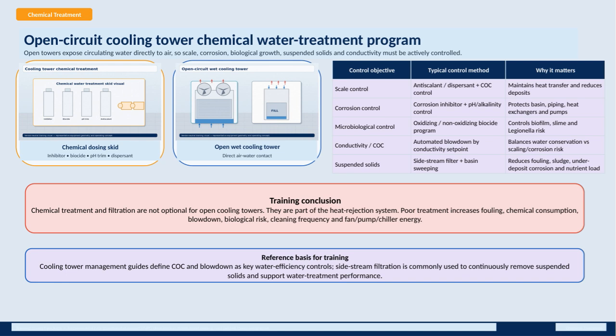These chemicals serve specific purposes. Antiscalants and dispersants help control scale formation. Corrosion inhibitors and pH adjusters protect the basin, piping, heat exchangers, and pumps, while biocides keep microbiological growth like biofilm and Legionella risk under control.